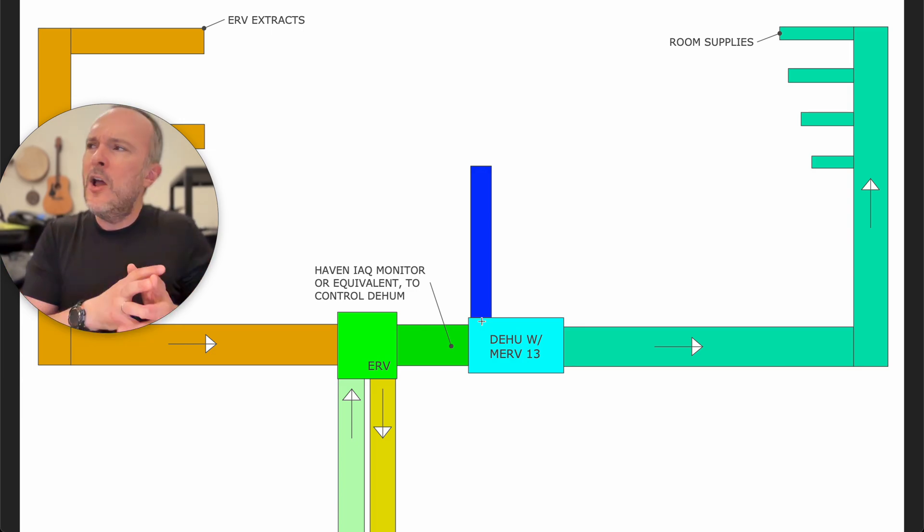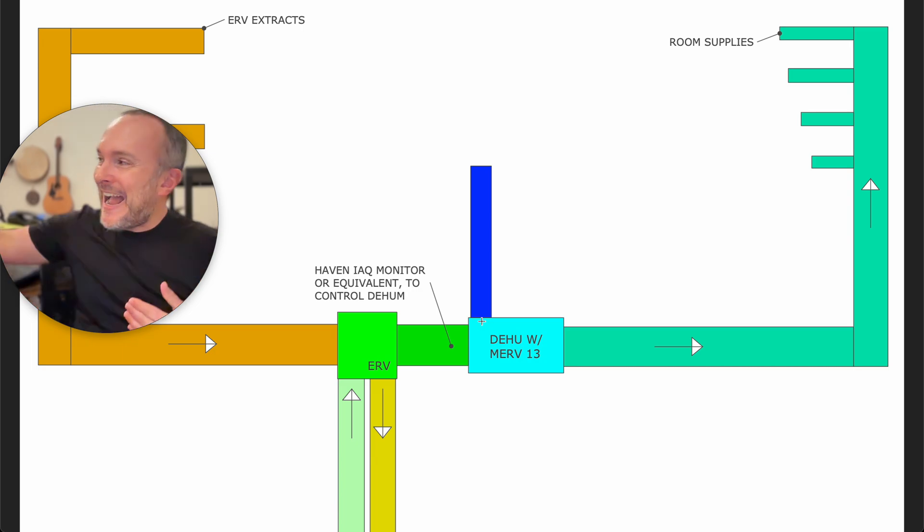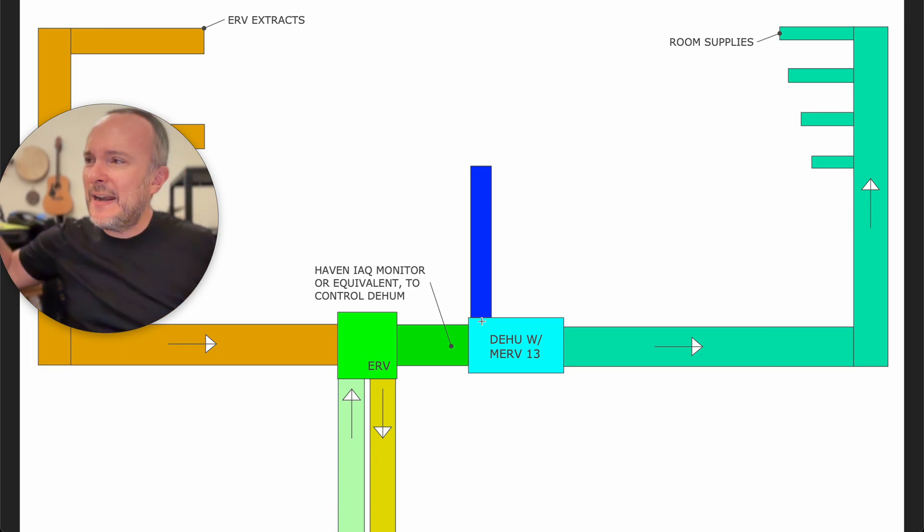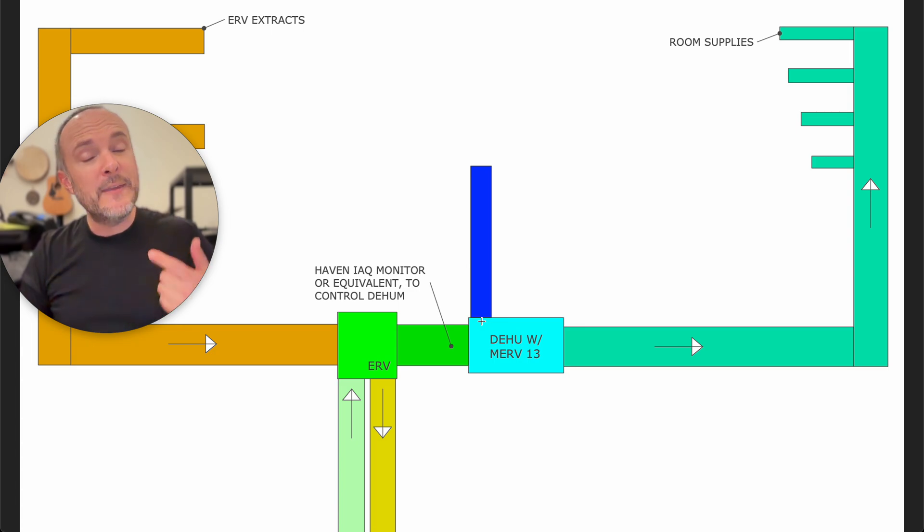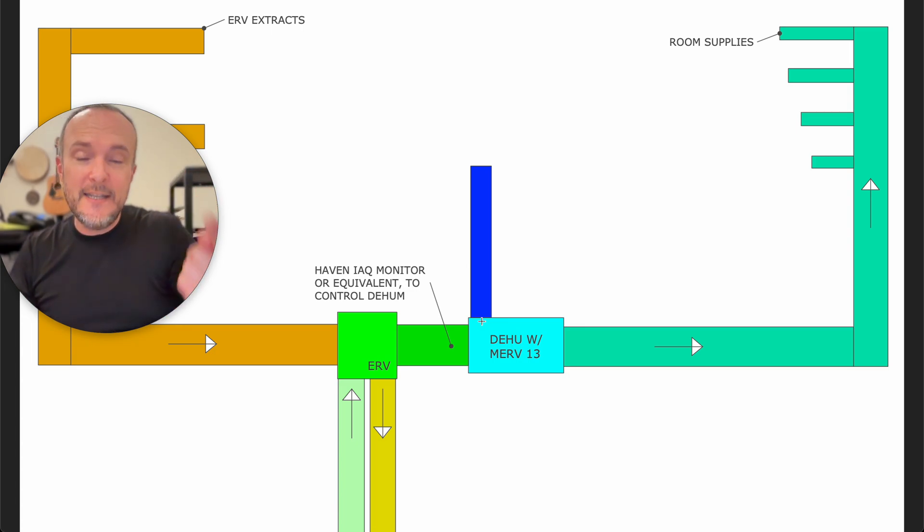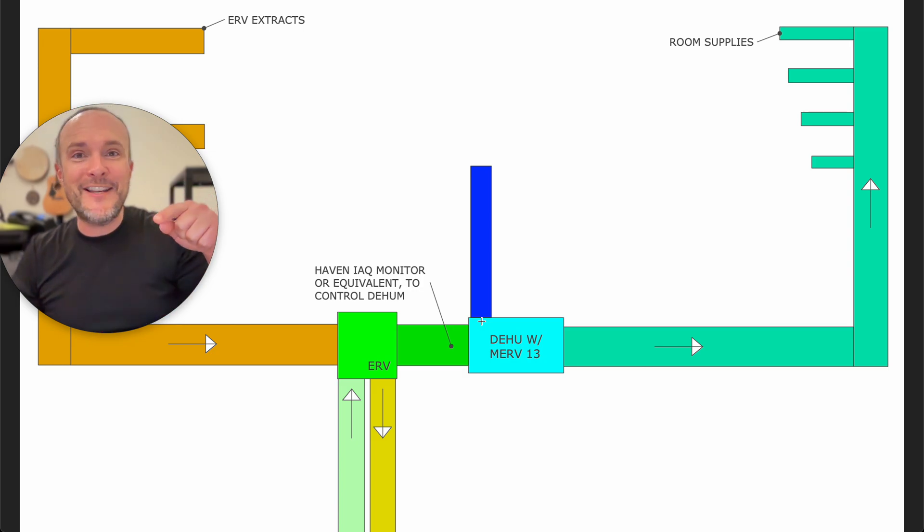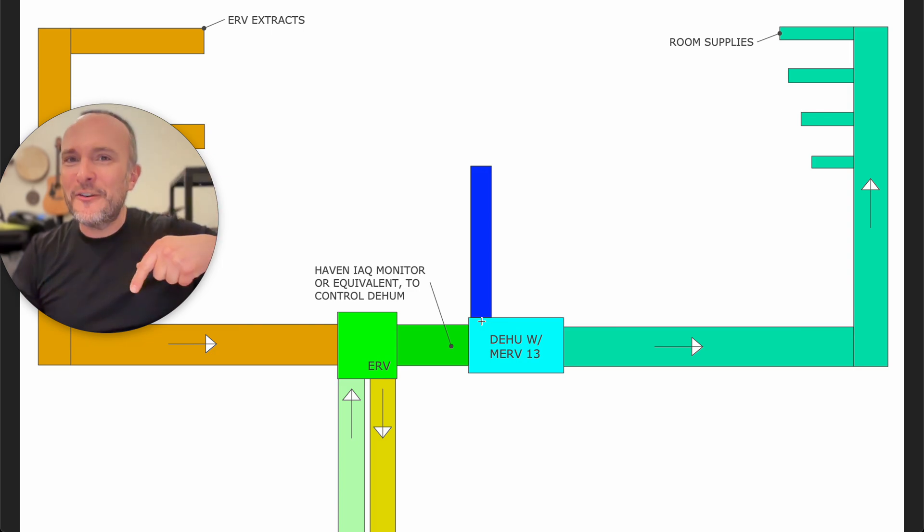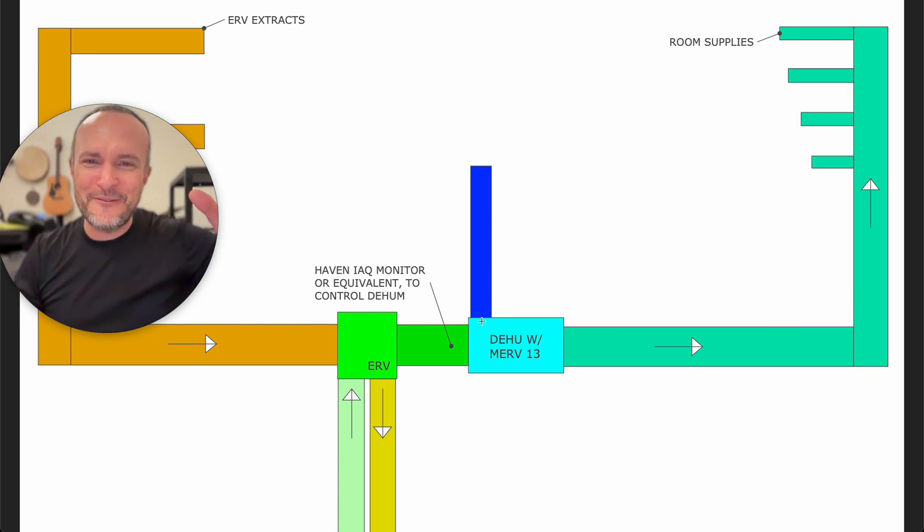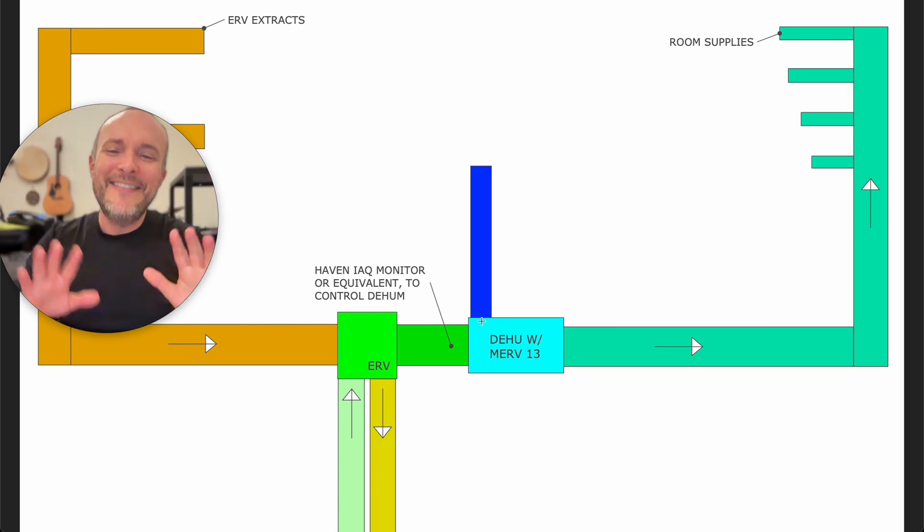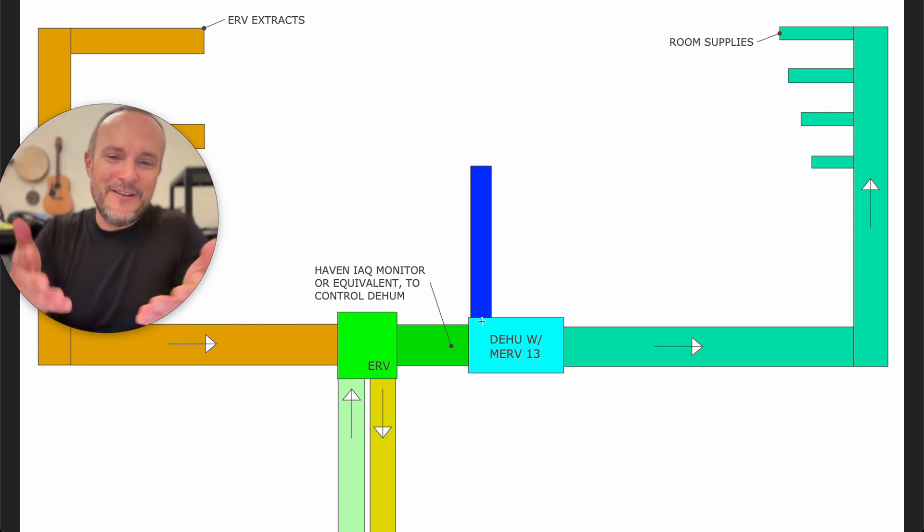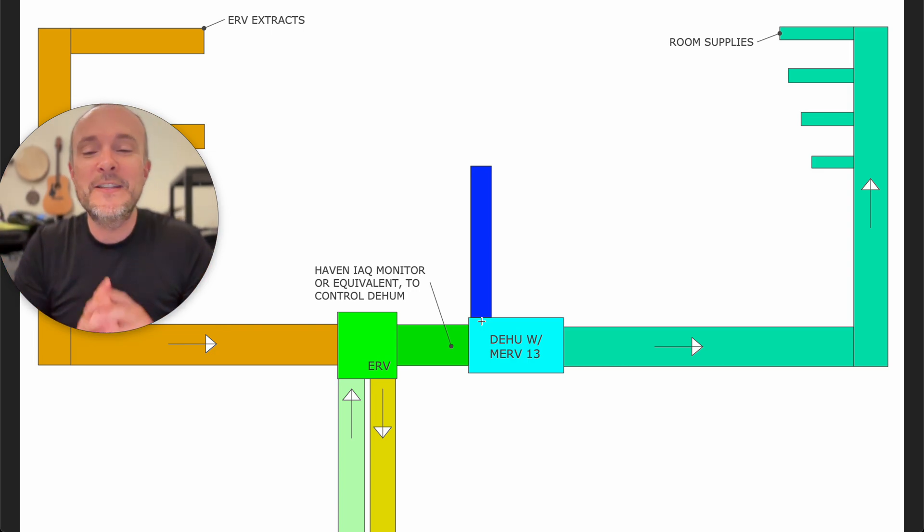Like for me, I had my humidistat in this room that I just installed last week and I'm like, 'It's not working, I don't know why.' I had to go in and tell the humidistat that it was running a dehumidifier, not a humidifier, so it was happy to turn on when it got under 50, but it wouldn't turn on if the humidity was over 50. Anyway, this is the kind of thing that, like, you start dealing with complex systems—it's just not going to get set up right. So you want to make sure that you think through all the possibilities.